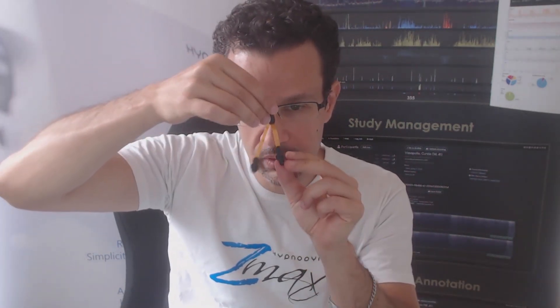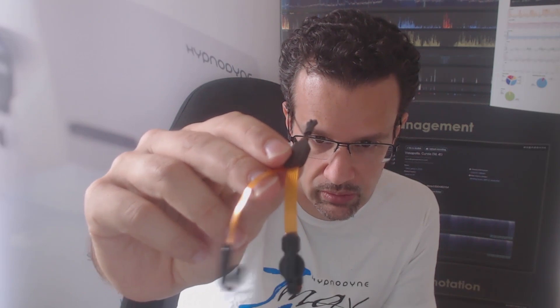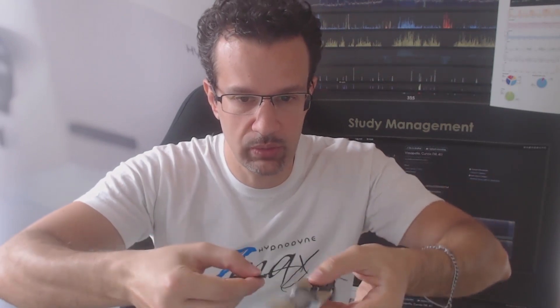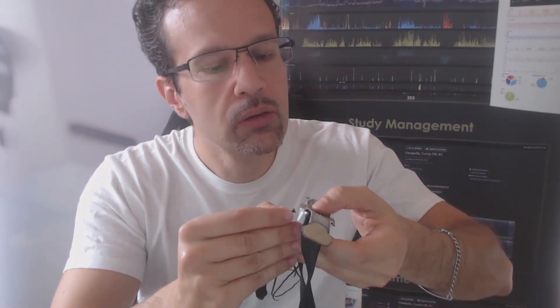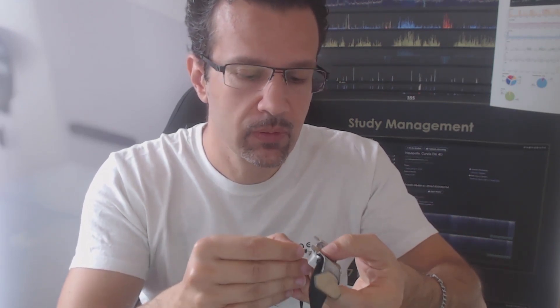If you hold the sensor this way, you will see that it has hooks. The hooks clearly need to get into your nostrils, so the hooks will be facing towards your face. When that is true, the part of the sensor with the arrow will be facing towards the outside, away from your face. When you mount it, you must be careful to align them correctly. You must position it correctly with respect to your face, looking at the side with the X, then find the port. These four pins on the sensor need to go into the four holes on the receptacle. Make sure the pins are properly aligned and don't use force — you have to look at the holes while it's going in.